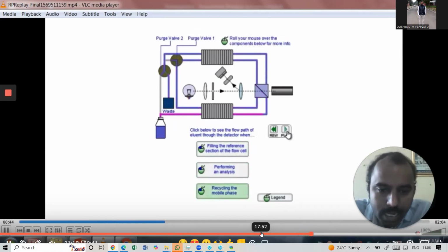However, this is very problematic in gradient HPLC systems, whereas in isocratic HPLC, your refractive index detector is the best detector for your analysis, because any change in solvent causes drifts, and a large change in refractive index causes very bad chromatographic signals in gradient HPLC systems.